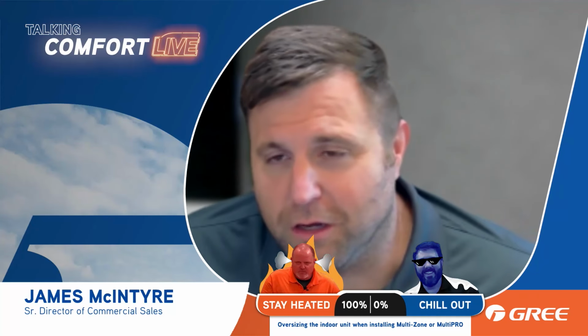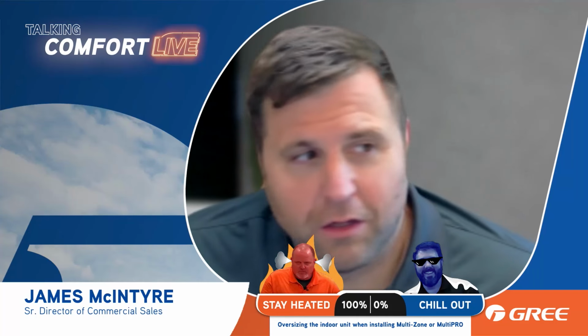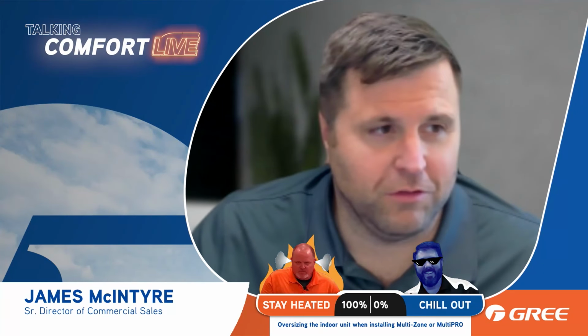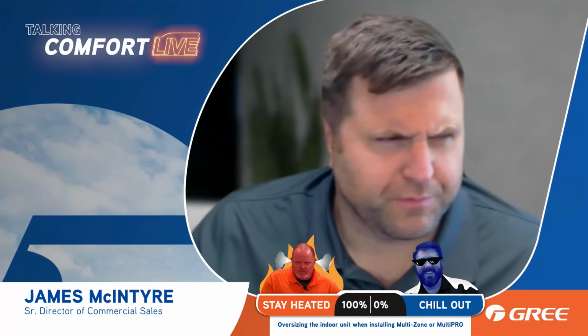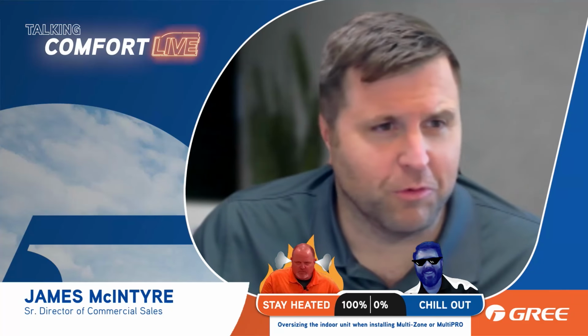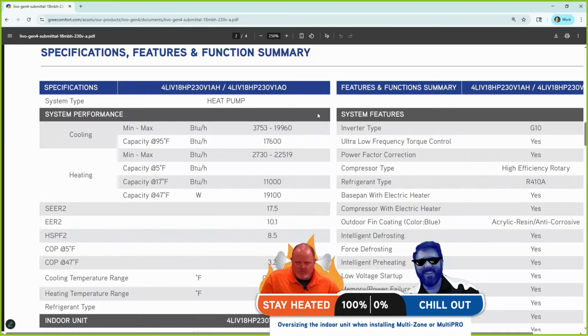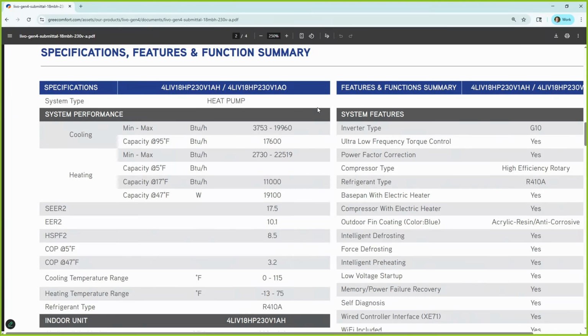So if I come on and I call for cooling, and I have to run at 2,388 BTUs, or in the case of this 18 that we're displaying right now, or that we can display, let's do that. We got an 18,000 BTU unit, 3,753 is the minimum amount. And if I've got to run for 6 minutes, that's the minimum amount of capacity that I'm going to provide. If your space can be cooled down providing only 3,753 BTUs and only running for 6 minutes at a time, it's too large, it's too big.